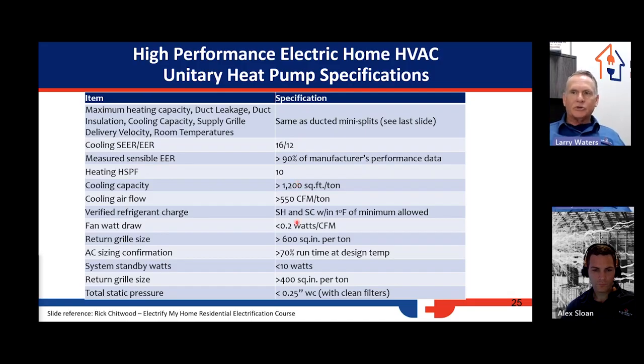Verified refrigerant charge. Return air grills should always be at least 600 square inches per ton with high performance. That's something else that's not getting hit out there. And we should never have our system standby watts more than 10, and the rest of the stuff. Always, the bigger return air grill and the bigger return air duct you can put on is going to give you the lowest static pressure. And you can do 0.25 water column with clean filters with a heat pump. It's really, really hard to do with a furnace and a coil. Heat pumps are easier.